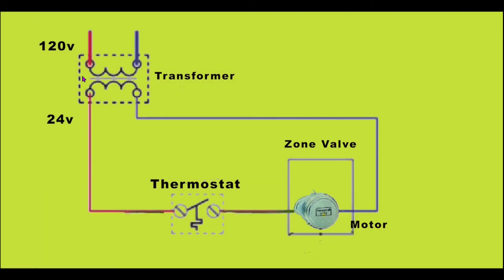So what we have here is a power source of 120 volts coming in to a transformer. Once it comes into the transformer, we have 24 volts going through the line that are controlled by a thermostat.